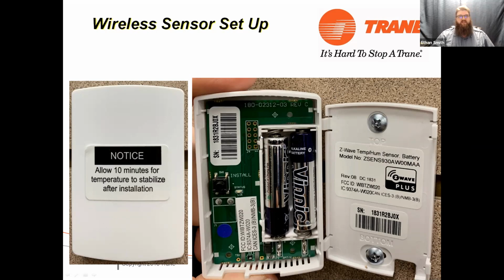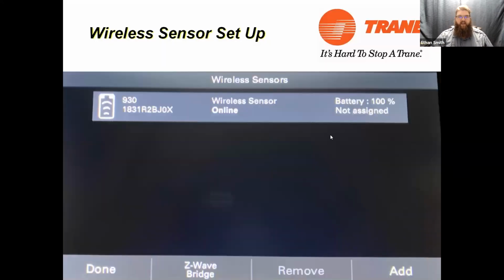You do have to be a little judicious of where you apply these wireless zone sensors. If you've got a house with a lot of interference, a lot of concrete walls, brick walls, metal studs, things like that are going to interfere with the wireless signal. The more interference you have, the harder that zone sensor has to work, the shorter the battery life you're going to see. So we do have a house that there was so much interference on the zone sensors that a pair of alkaline batteries was lasting 2 weeks. So A, use the lithium batteries, and B, be judicious where you use these wireless sensors. Make sure you're not going to cause yourself more problems down the road. They definitely have their place though.